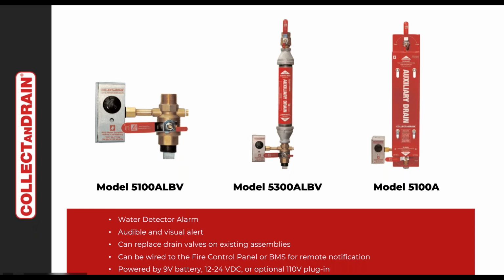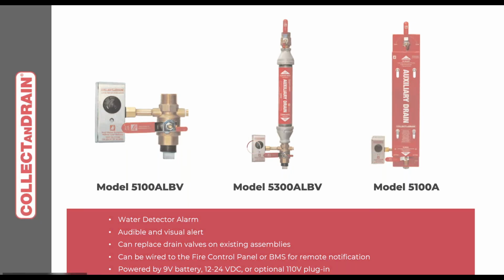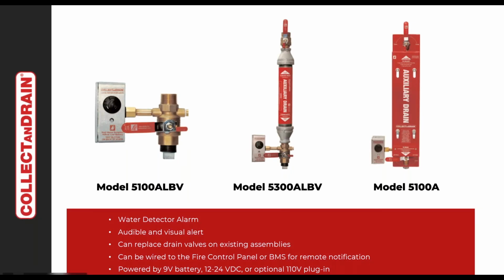So we introduced the model 5100 ALBV, and the ball valve here that's at the bottom, located on the bottom of the valve of a low point drain, well, it will chirp and blink locally. It's got a little speaker and it's got a little blinking LED light. So it will chirp and blink to tell you that this is the low point drain and it has accumulated water and needs to be emptied. So again, thinking back to what happened in Texas, here's an environment where the person could say, hey, this thing's chirping and blinking like the low battery alarm on a smoke detector. I better go get the moisture out of this because the temperature's starting to plummet.